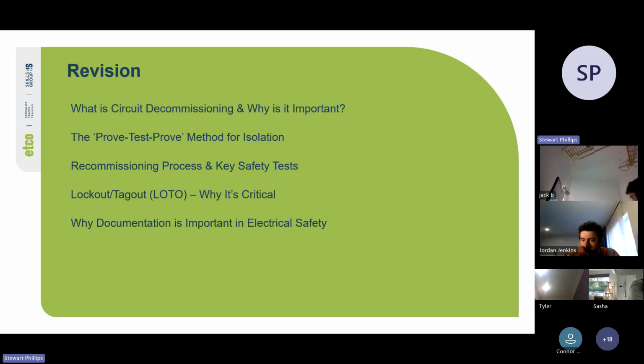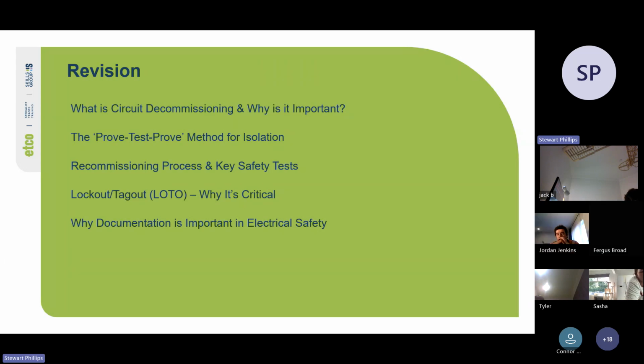Cool, so recommissioning process and key tests - I'll just go through this. After decommissioning circuits, we must test before re-energizing. AS/NZS 3017 verification and testing, and AS/NZS 3760 testing and tagging, outline key tests. So you've got your insulation resistance test, or IR test, to ensure wiring insulation is intact. Your earth continuity test confirms a safe path to earth, and your polarity test ensures active, neutral, and earth conductors are correctly connected. And the equipment must be fully tested and documented before being put back into service.